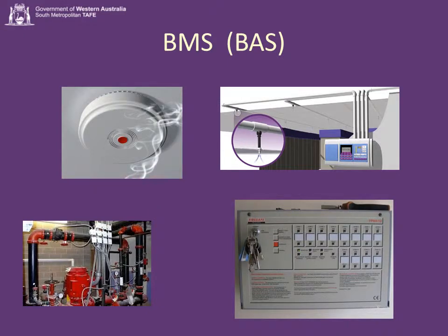We can interface with the fire system. This allows us to set the air handlers into the appropriate modes when fires occur, so that we can pressurize staircases and pressurize the rooms adjacent to the fire.